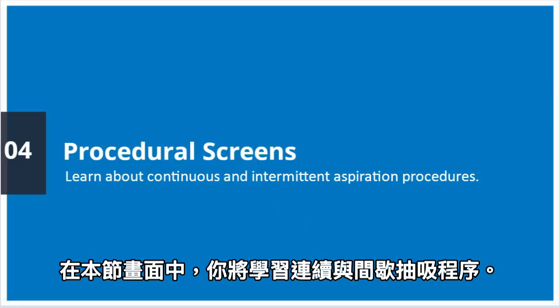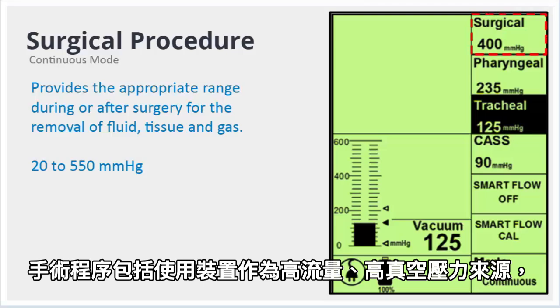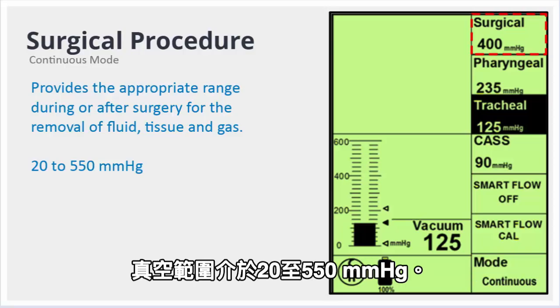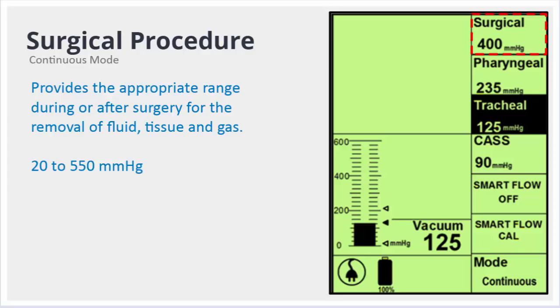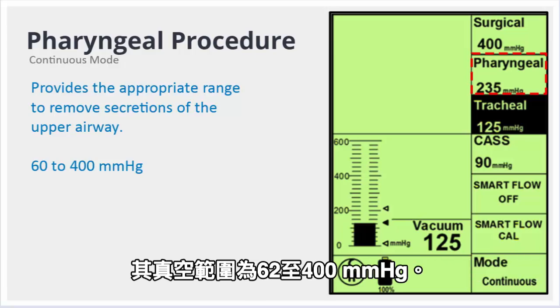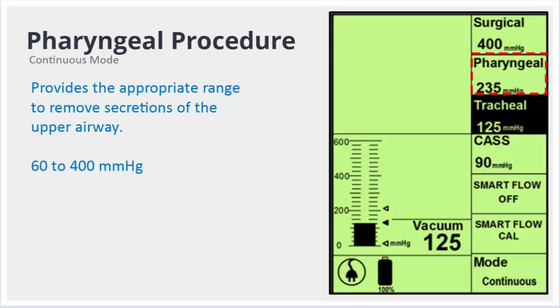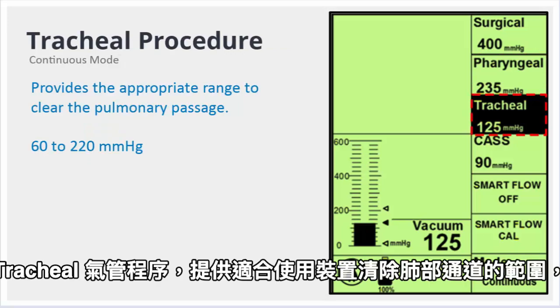In this Procedural Screens section, you will learn about the continuous and intermittent aspiration procedures. The surgical procedure includes using the device as a source of high flow and high vacuum pressure to remove fluid, secretions, or debris from cavities, wounds, or other surgical sites, with a range between 20 to 550 millimeters of mercury. The pharyngeal procedure provides the appropriate range to remove secretions of the upper airway, such as the mouth and throat, with a range between 60 to 400 millimeters of mercury. The tracheal procedure provides the appropriate range for the use of the device to clear the pulmonary passage, which is between 60 to 220 millimeters of mercury.